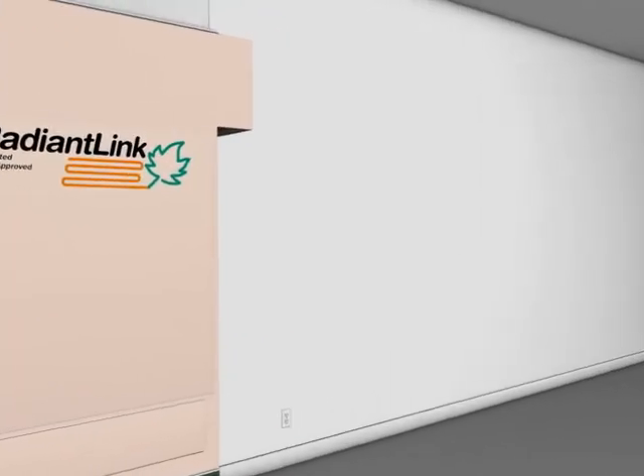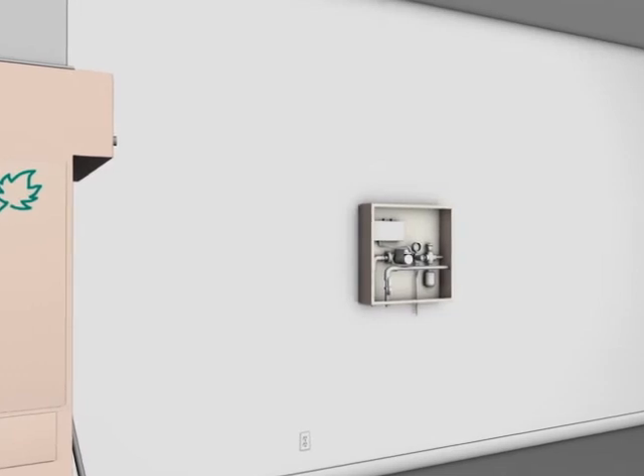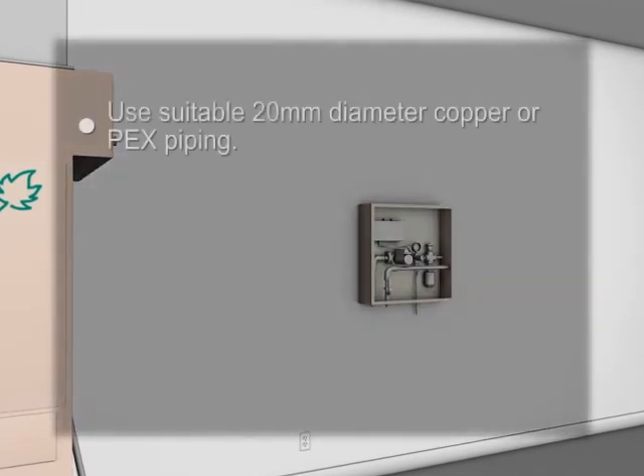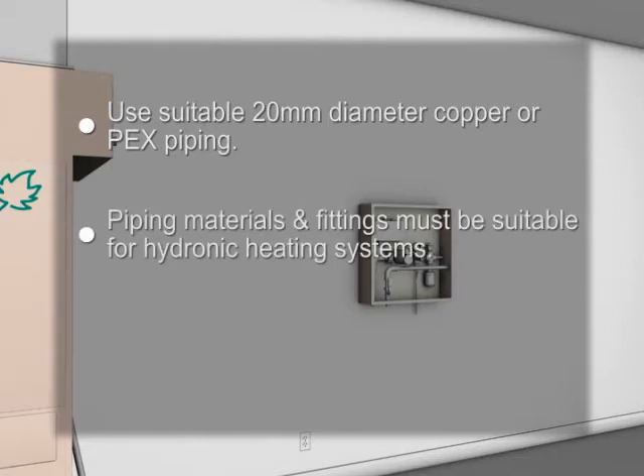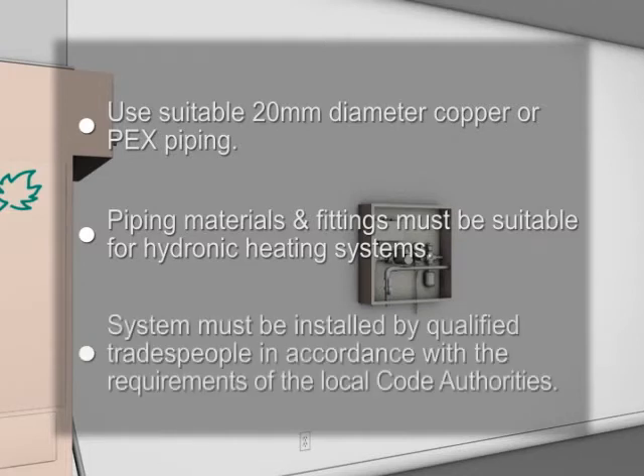Securely mount the control panel to a wall in the furnace room. Use suitable 20 mm diameter copper or PEX piping and fittings to connect the control panel to the plenum coil and to the radiant floor or wall manifolds. Remember that the piping materials and installation practices must be suitable for hydronic heating systems and installed by qualified tradespeople in accordance with the requirements of the local code authorities.